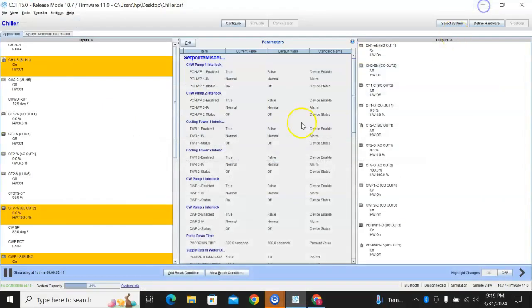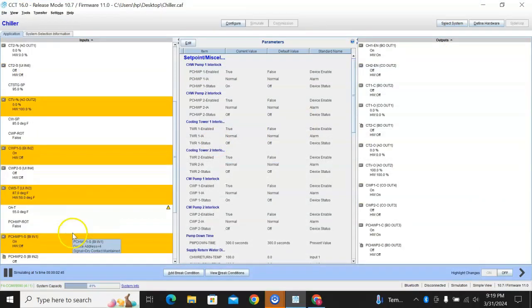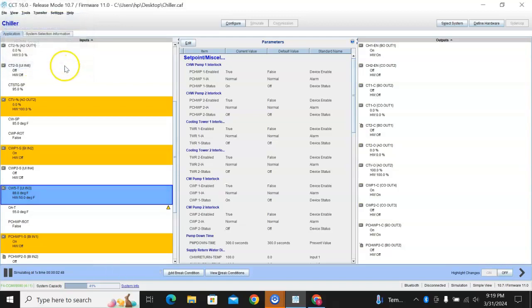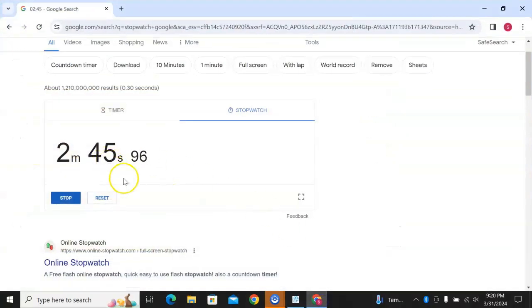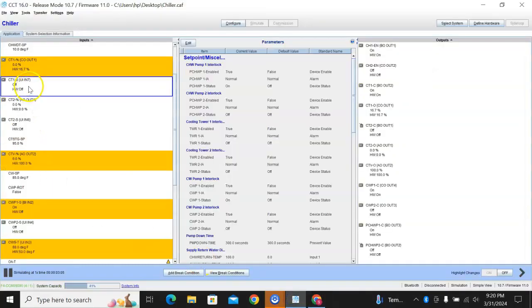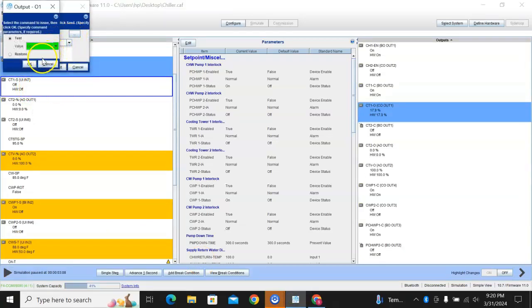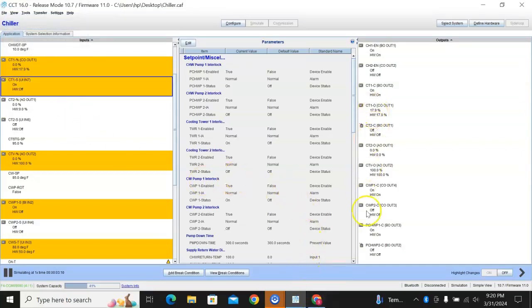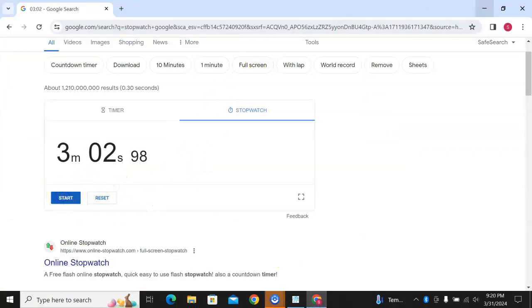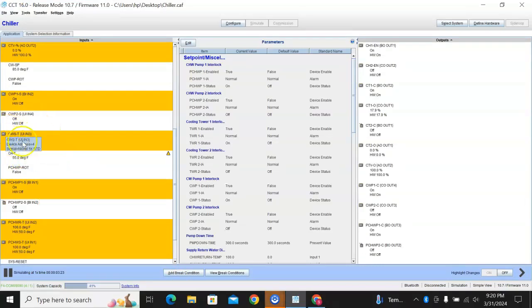Check my time. 2 minutes. Go ahead and add. 88. There it is. It's on. Show you the time. Go back. Hit my status on. Show you the time again. Look, we're already at 17%. I'm going to stop it. So 3 minutes in. And I think I was pretty fair on increasing the temp. We're at 88 degrees. So we're 3 degrees off of the set point, and we've already got the fan on, and the fan's already starting to ramp up.